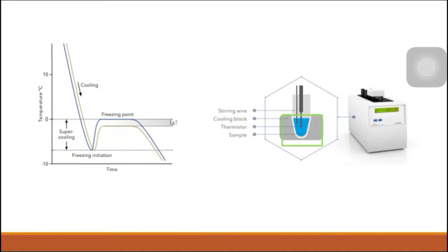So, the resistance to current flow is inversely proportional to the temperature, such that the resistance to current flow increases as the temperature falls. So, if the resistance to current flow is high, the temperature is low. The temperature at which a solution freezes can be determined by measuring the resistance of the thermistor.